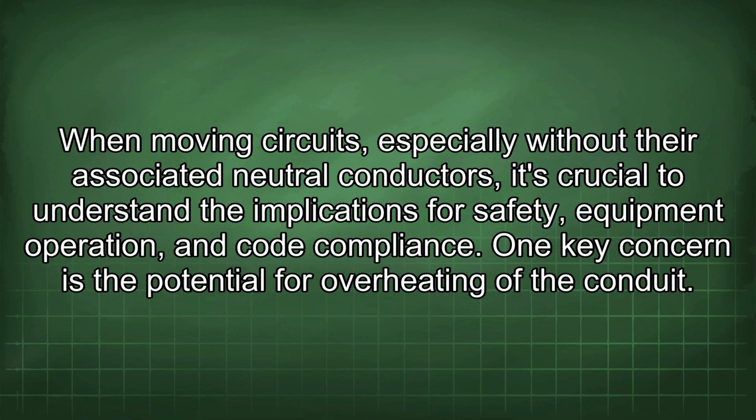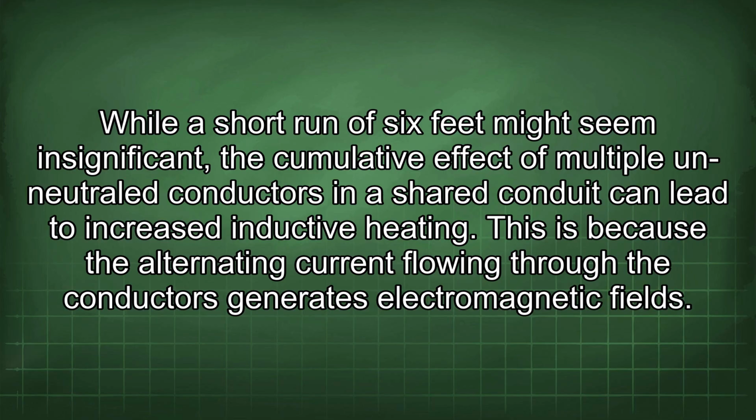code compliance. One key concern is the potential for overheating of the conduit. While a short run of 6 feet might seem insignificant, the cumulative effect of multiple unneutralized conductors in a shared conduit can lead to increased inductive heating. This is because the alternating current flowing through the conductors generates electromagnetic fields.